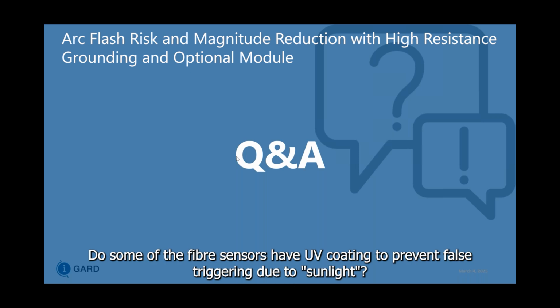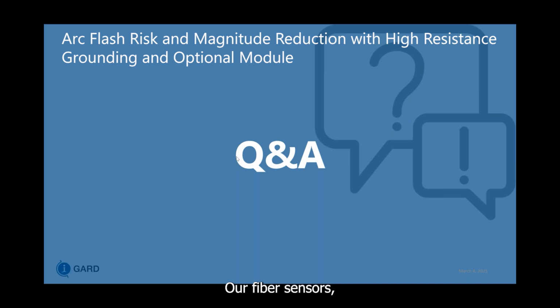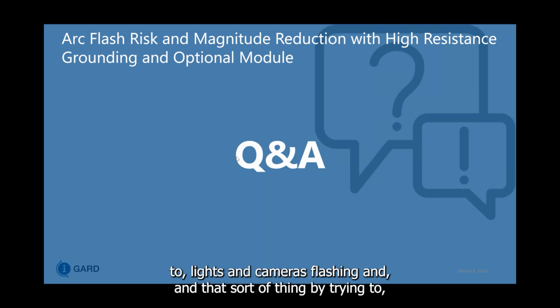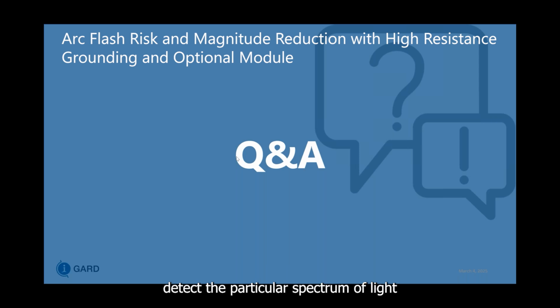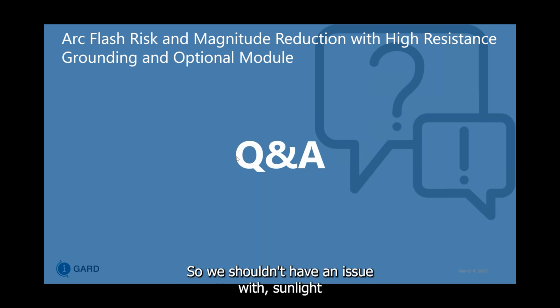Do some of the fiber sensors have UV coating to prevent false triggering due to sunlight? Our fiber sensors, I don't think that they have a UV coating. I'm not 100% sure, but I know that we are trying to mitigate nuisance tripping in relation to lights and cameras flashing and that sort of thing by trying to detect the particular spectrum of light emitted by an arc flash incident. So we shouldn't have an issue with sunlight triggering the arc flash on these sensors.